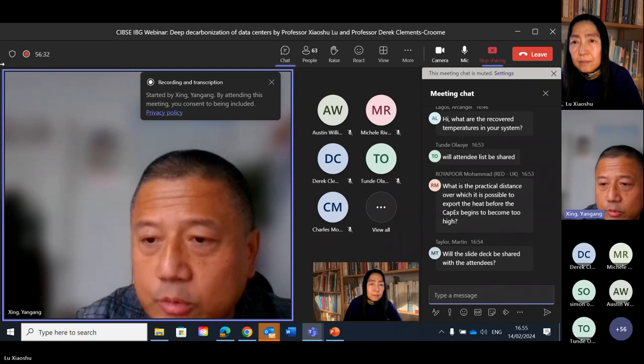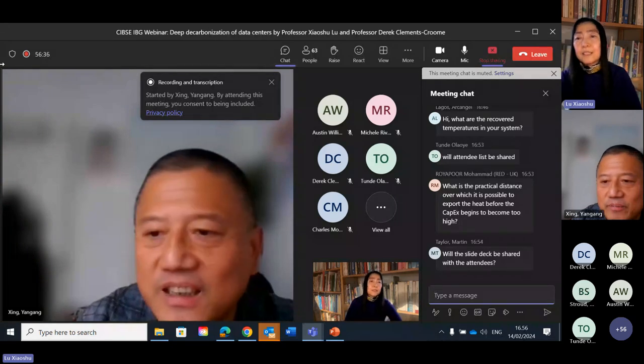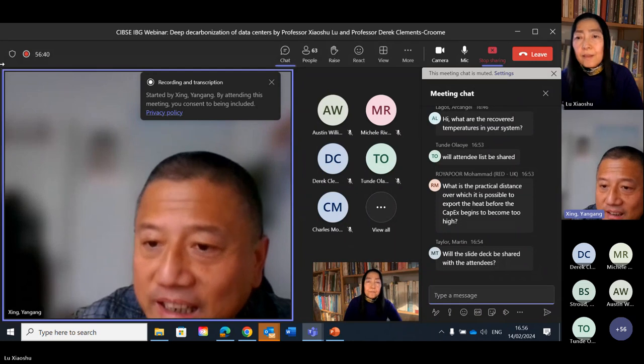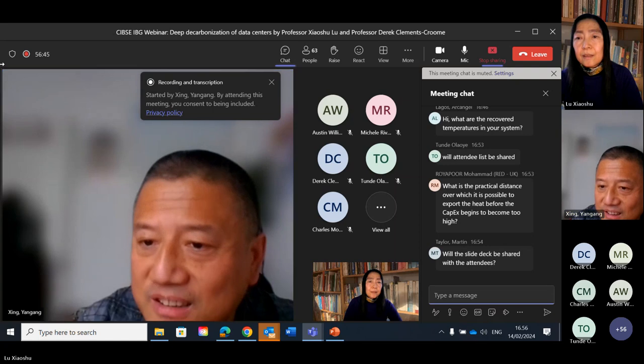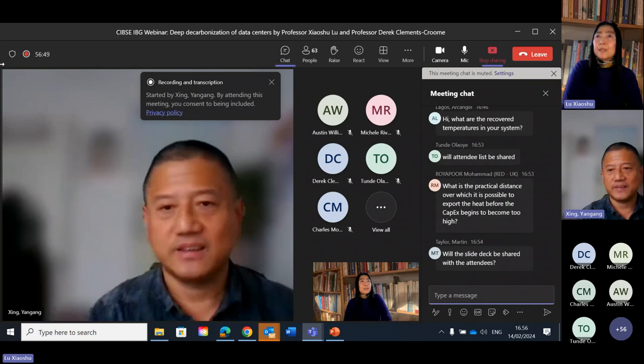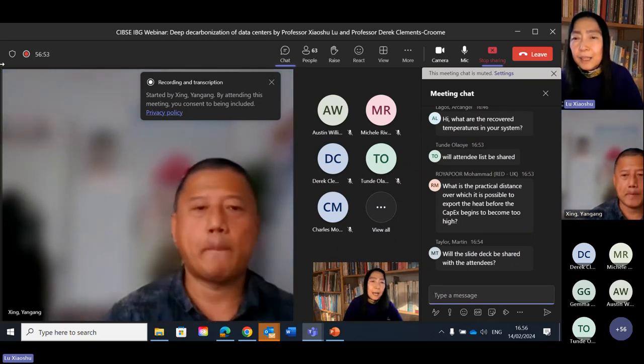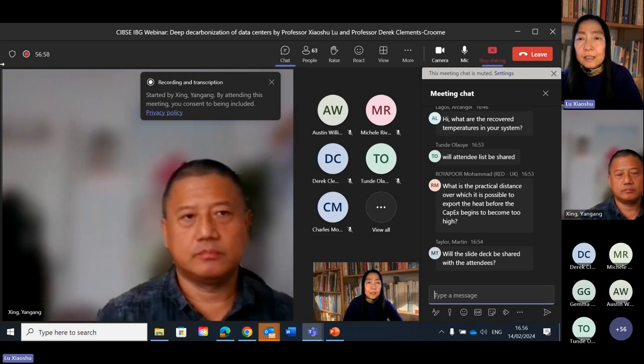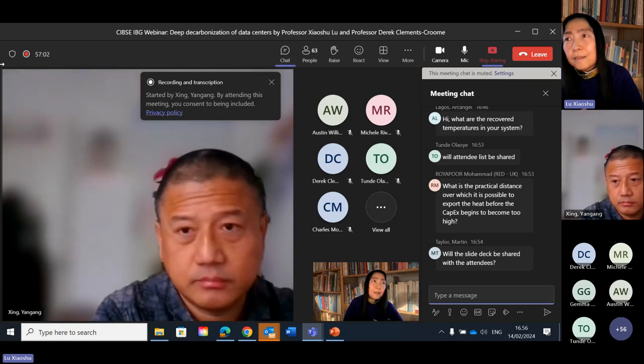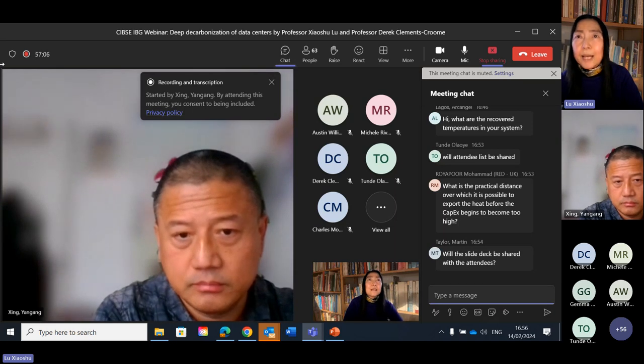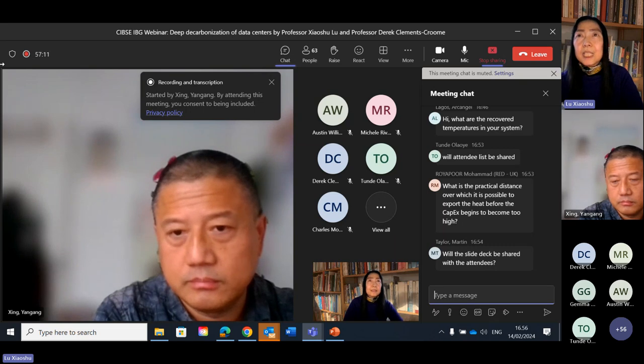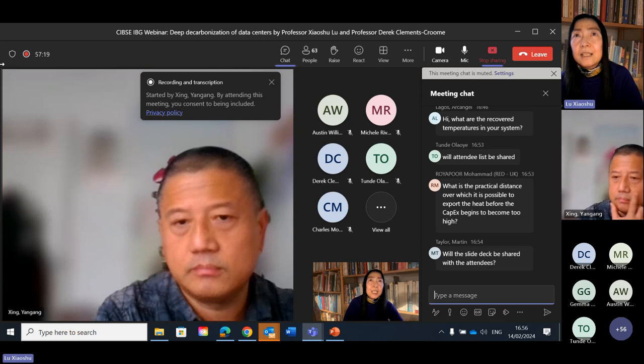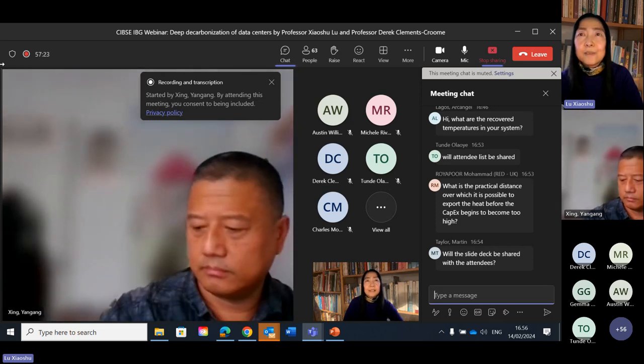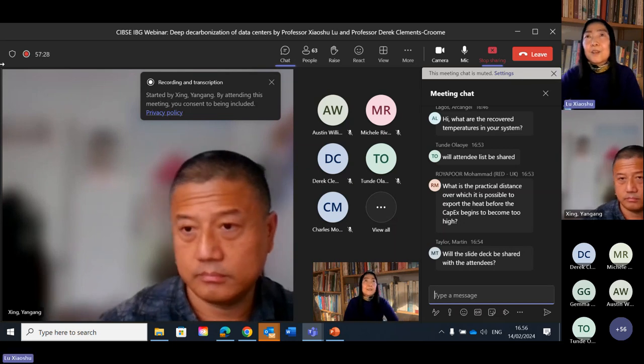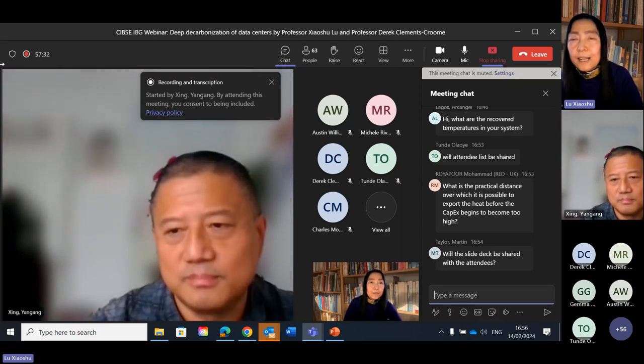Next question: what is the practical distance over which it is possible to export the heat before CapEx begins to become too high? What do you mean by practical distance? Is it physical distance? Yes. I can answer this way: the major cost is the piping. Heat exchangers are not very expensive. That's why we propose that these racks are not very far from the buildings. In Finland, the cost is 70 euros per meter, so then you can calculate that. If it's very, very far for a standalone data center, our method doesn't work because it's too expensive.